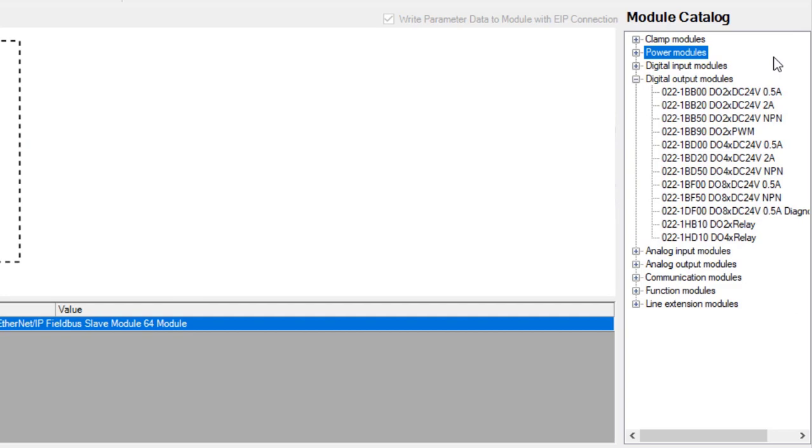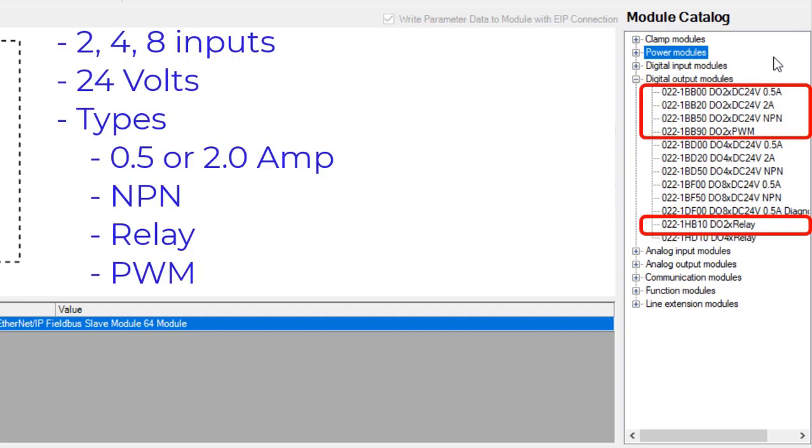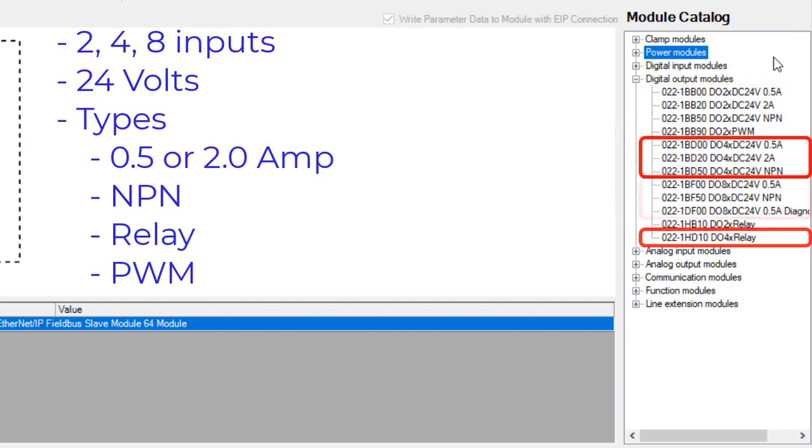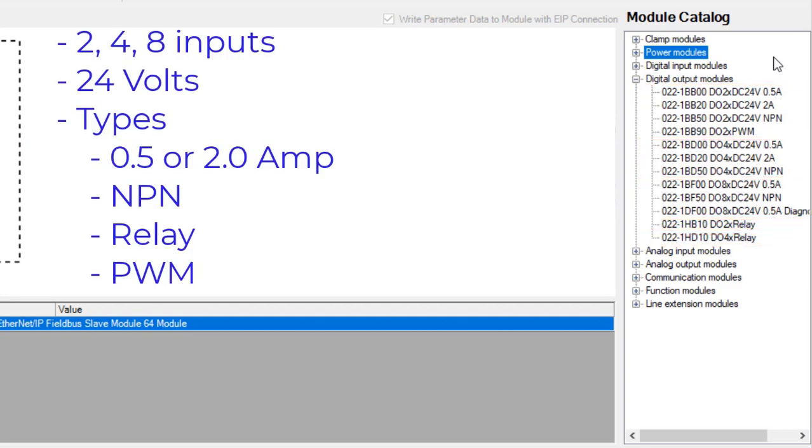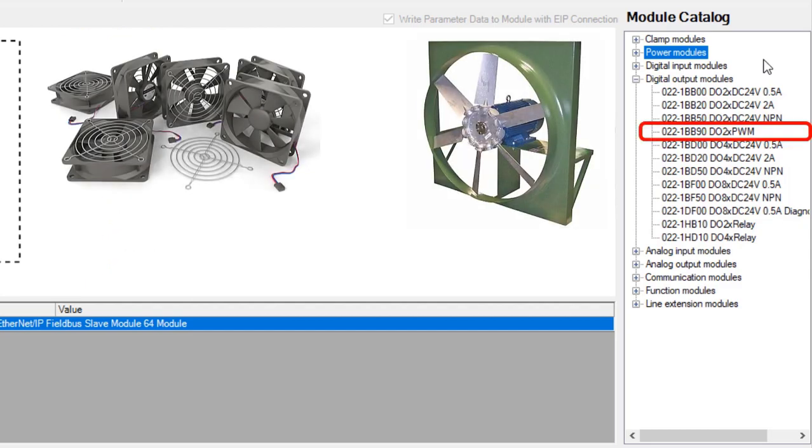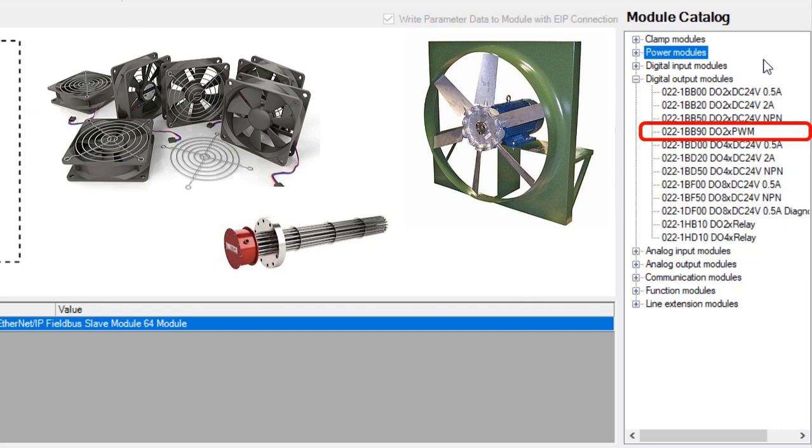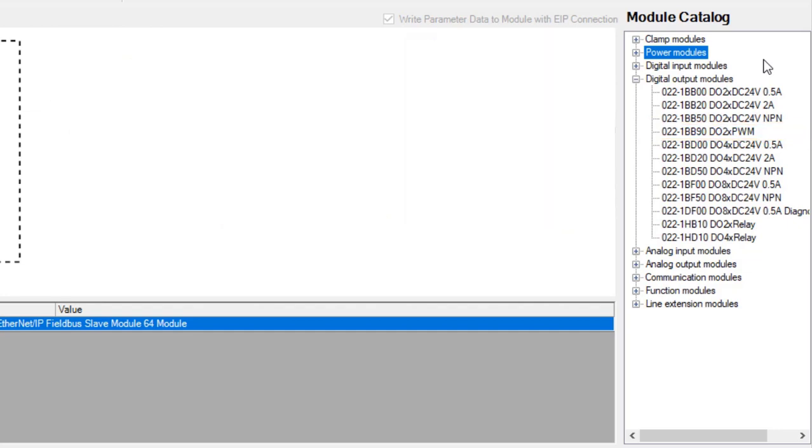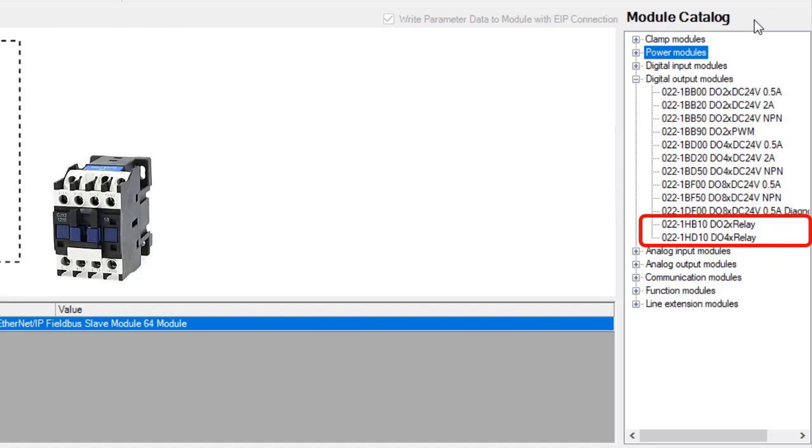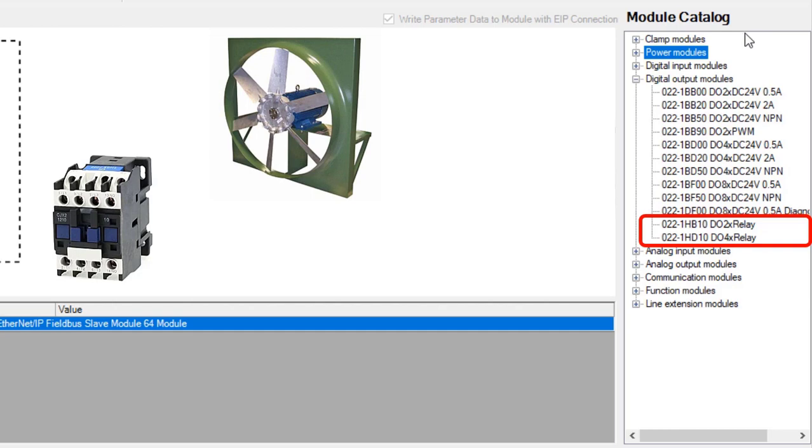Digital output modules are available also in 2, 4, and 8 outputs per slice. These slices work with 24V devices. Different modules are available for different applications. For instance, the PWM module is made to control simple fans, heaters, and other PWM controllable devices. Where the relay module allows switch control of higher voltage and current devices in applications like motor contactors, fans, and horns.